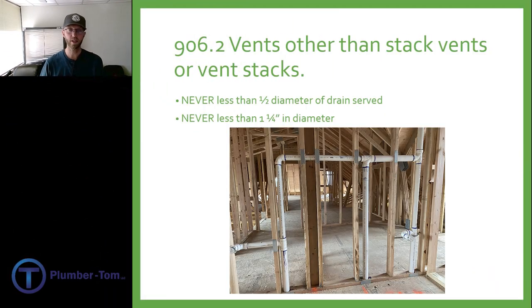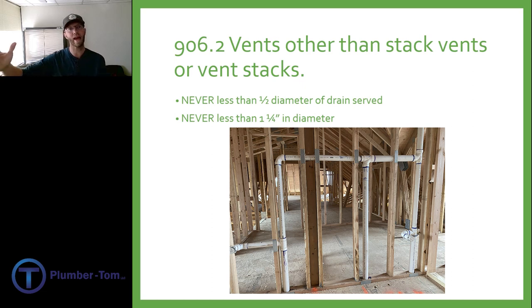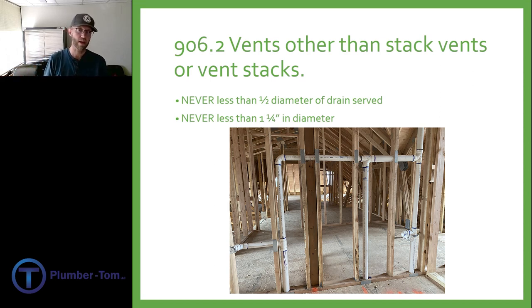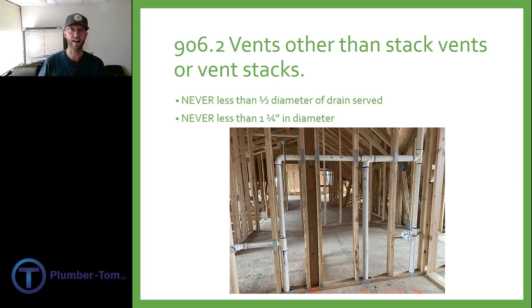Please be aware that 906.1 provides a table to size these vent pipes — we will look at that in a minute. Section 906.2 talks about vents other than stack vents or vent stacks. Stack vents and vent stacks are your main vents going out, and we tie other vents to those in many cases. Those other vents have this similar rule of never less than half the diameter of the drain served and never less than one and a quarter inch diameter pipe.